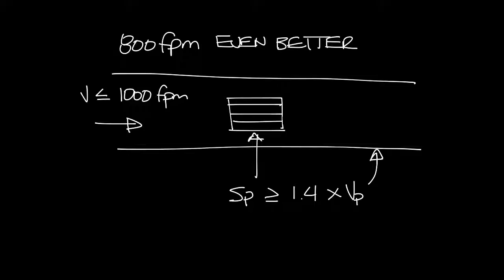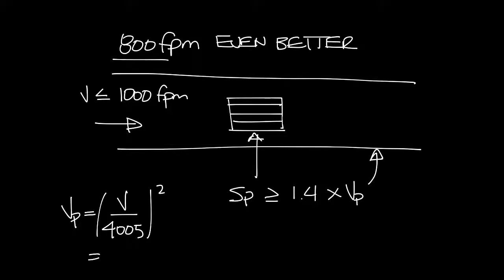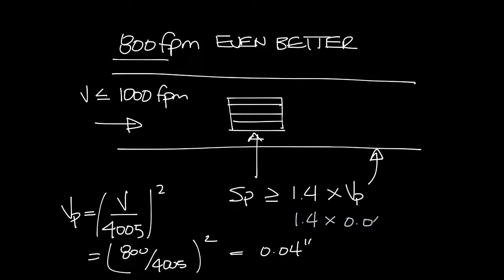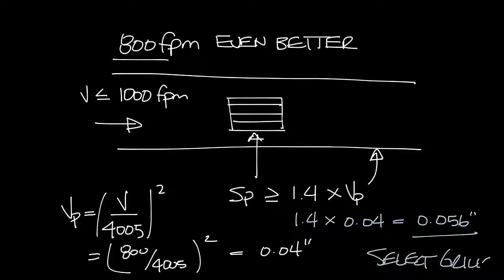So let's look at this. If you remember from one of the previous podcasts, velocity pressure equals the velocity divided by 4005 squared. And let's say we have 800 feet per minute here, so we'll do 800 divided by 4005, square that, and you get 0.04 inches. So let's take this up here and say 1.4 times 0.04, and that equals 0.056 inches. So you want to select a grill for this duct that has a static pressure of 0.056 inches or greater.